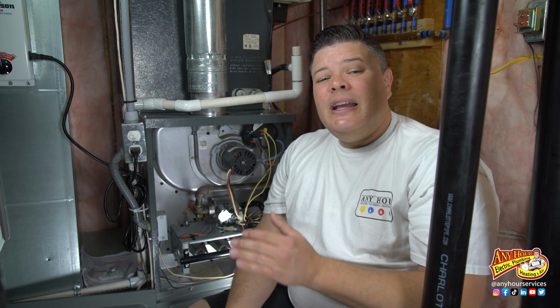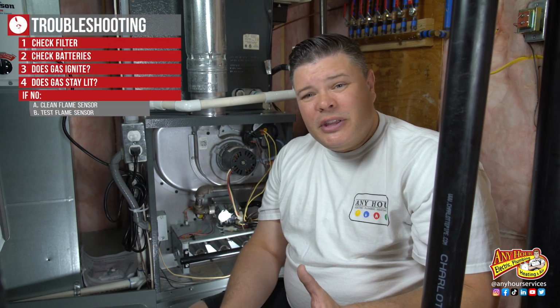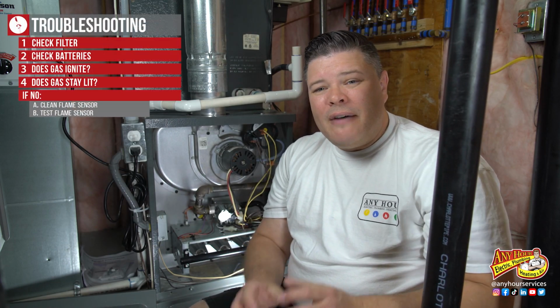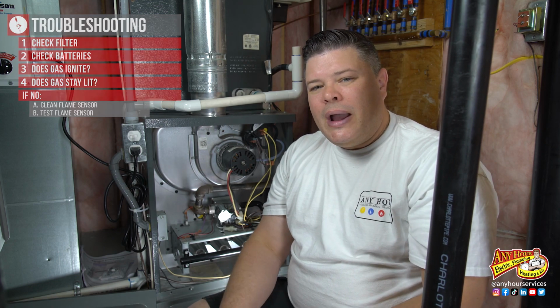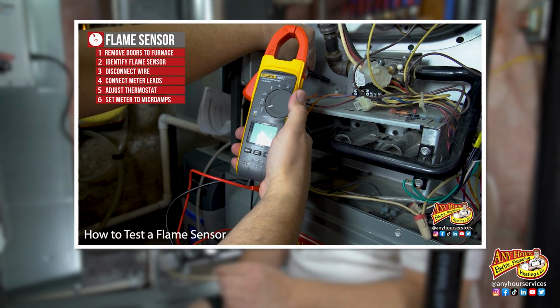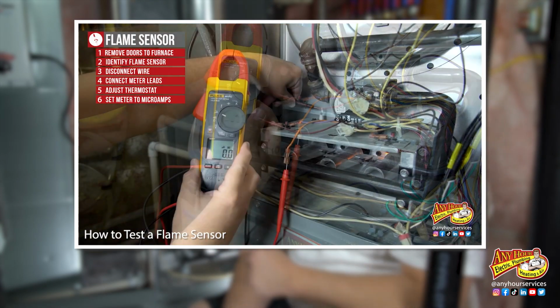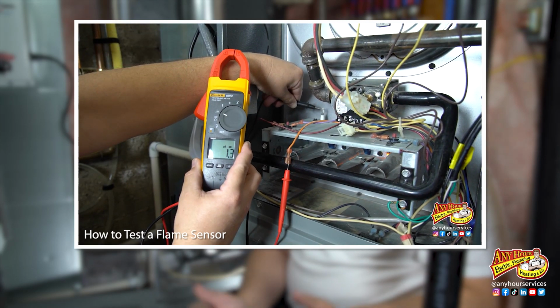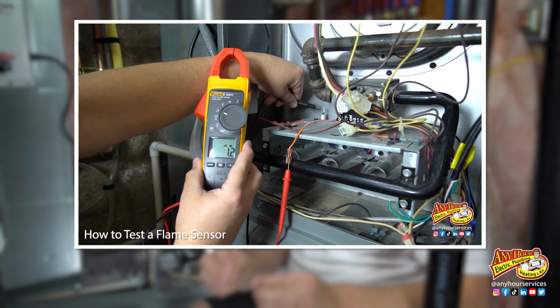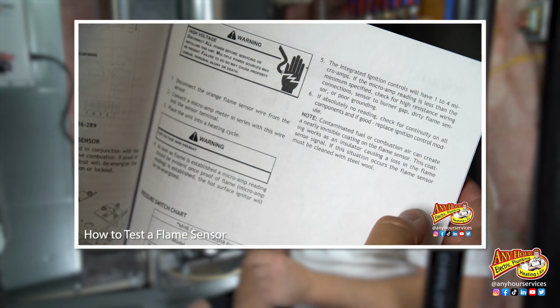If you tried cleaning it and that didn't work, it's possible that the flame sensor has gone bad. If you have a meter that can actually measure microamps, you can check to see if the flame sensor is still working. We actually made a video, we put a link down in the description on how to test the flame sensor. That's the next thing that you can troubleshoot.